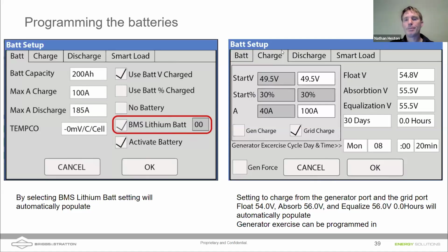On the battery setup tab, this allows you to set the charge rates from grid or generator port. Now these refer to the ports, so you can set the start voltage at which charging will begin from the generator port, and you can set that as a state of charge. So you can either do things based on a voltage or a percentage state of charge. That depends on what you have chosen in the basic setup tab, whether you view your battery information as a state of charge or a voltage. Again, the similar settings are available for charging off the grid. Once you hook up our communicating batteries, these numbers will automatically populate for you. I've given them down at the bottom of the screen.